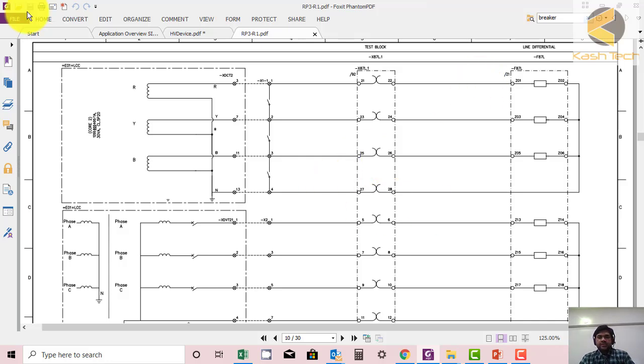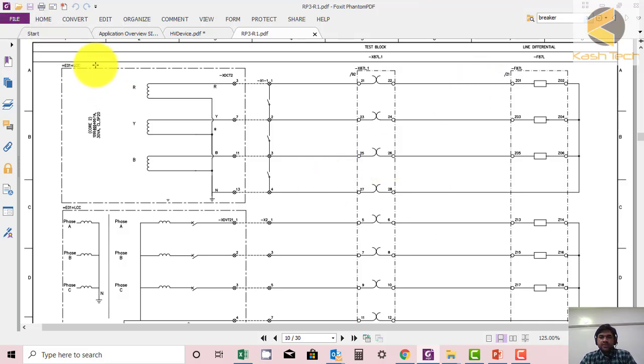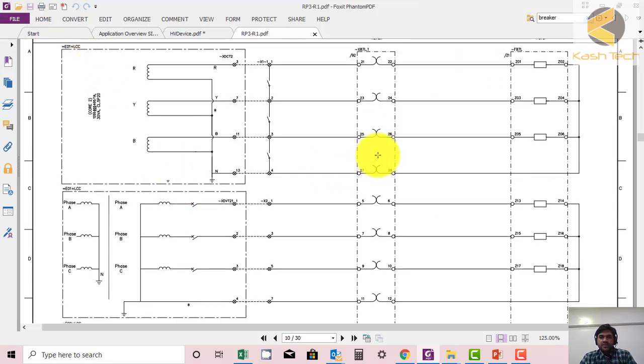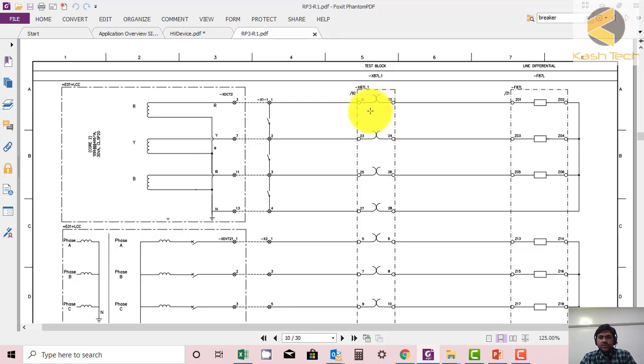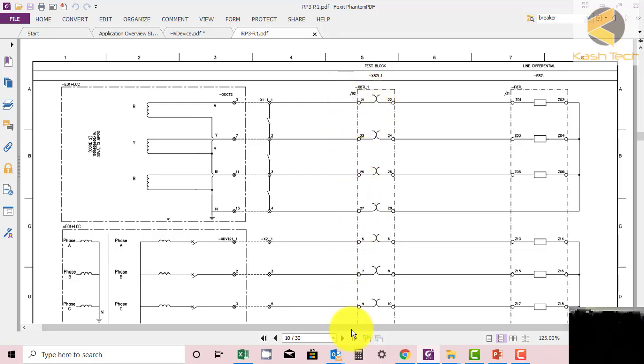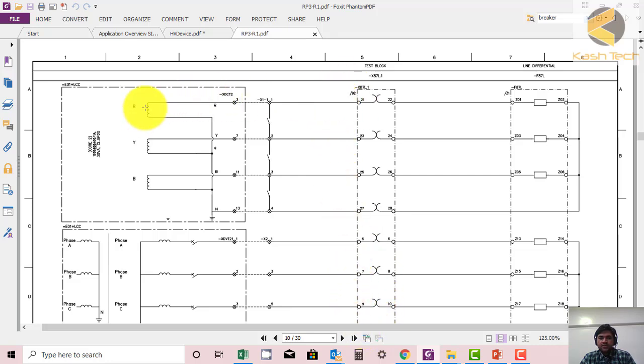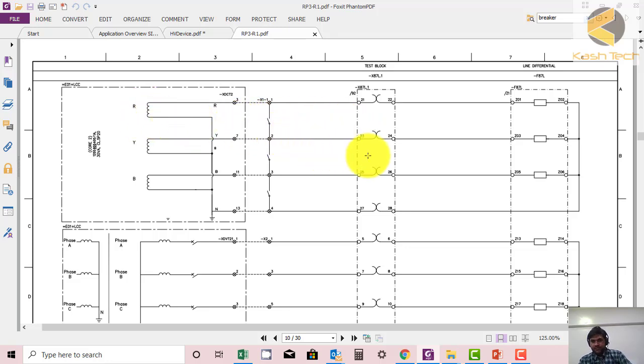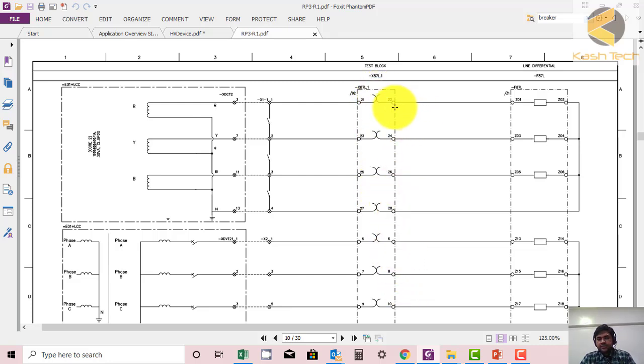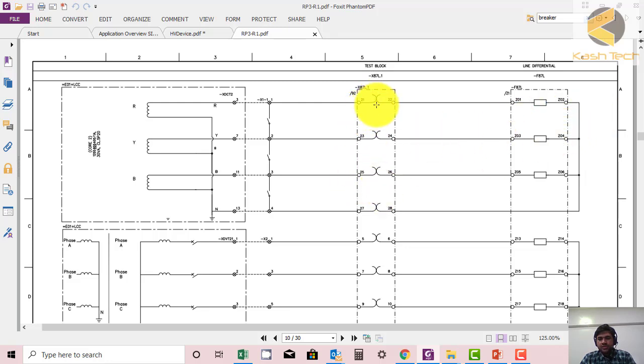The relay will issue the trip command. This is a test block. If you insert the plug, these two points will be open. The 21 side is the odd side. The protection engineer is calling this the yard side, because you can see the connections are coming from switchyard or external side to this plug. The even side - in our language - is the relay side. When you insert the plug, it will put insulation between 21 and 22 and isolate the yard side from the relay side.